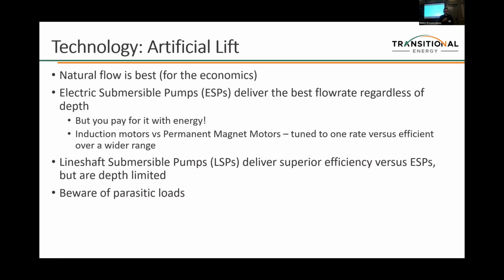So artificial lift is one of those areas you can't avoid when looking at a full scope geothermal opportunity. There are line shaft submersible pumps, where the line is a shaft that goes down into the subsurface, sometimes up to 1, 2, or maybe even 3,000 feet, but the longer the dicier. They deliver better efficiency than ESPs and are more power efficient, but tend to be a little limited on the depths they can work with.